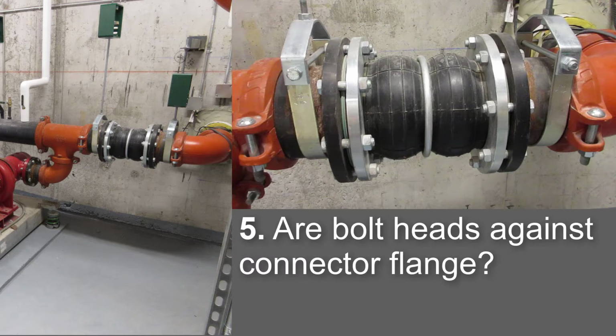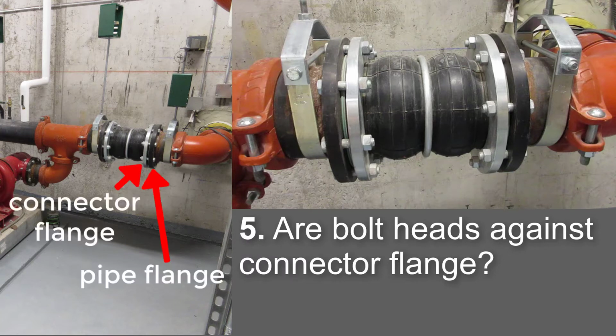Fifth, are the flange bolt heads up against the connector flange? Well, no they aren't. I'm not sure why contractors often install them this way, but it presents a higher risk for damage to the body of the expansion joint since typically the bolt head is held in place while the nut is turned with a wrench. A slip while tightening a nut could result in the sharp edge of a wrench going into the side of the joint. Further, if the flange bolts are very long, they could run into the side of the joint during system operation movements and cause damage to the body of the joint.